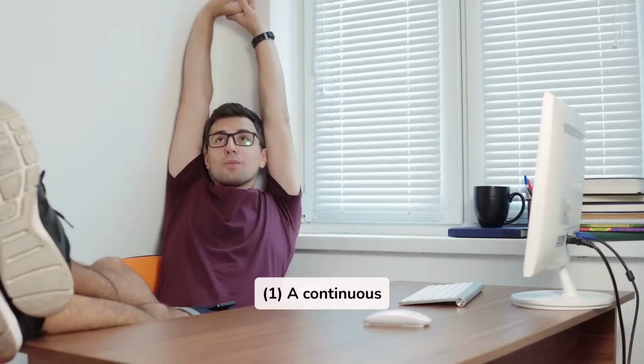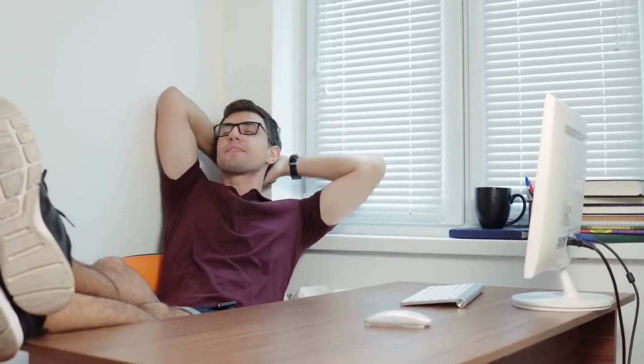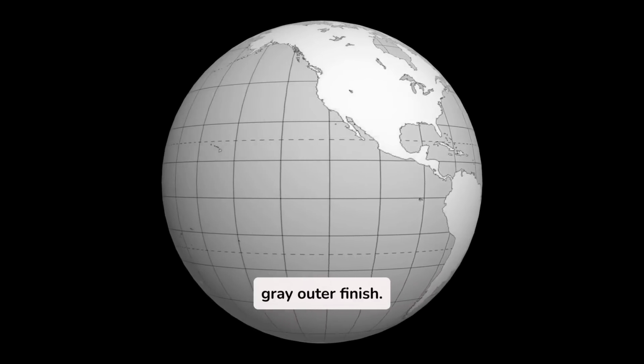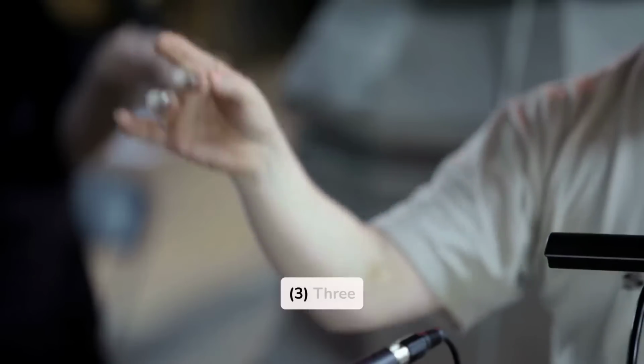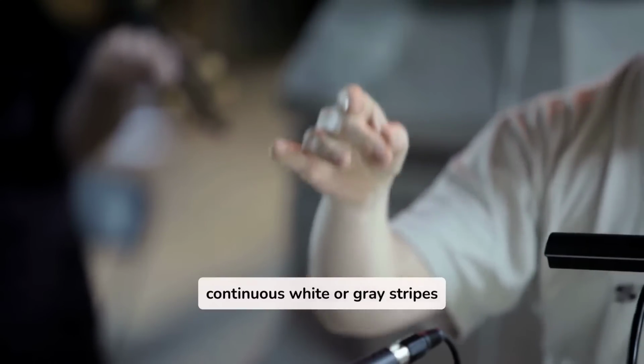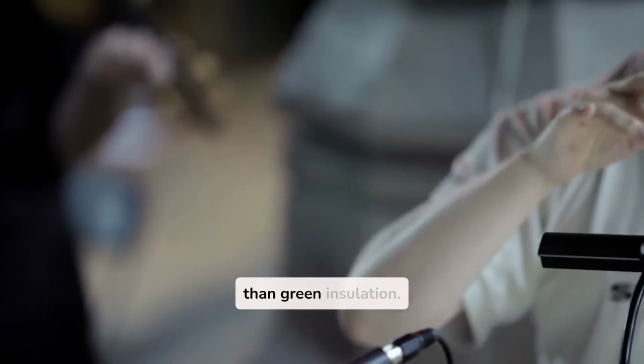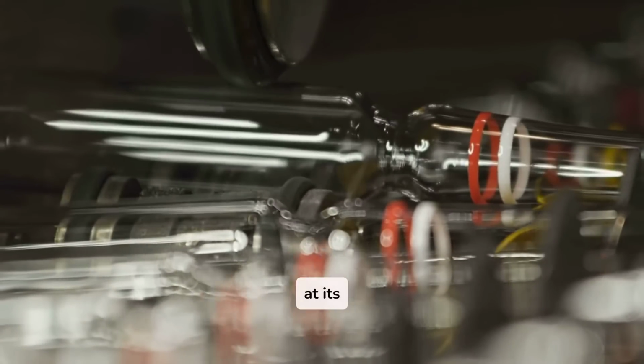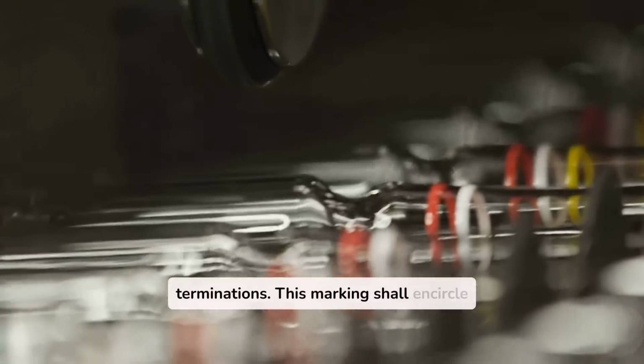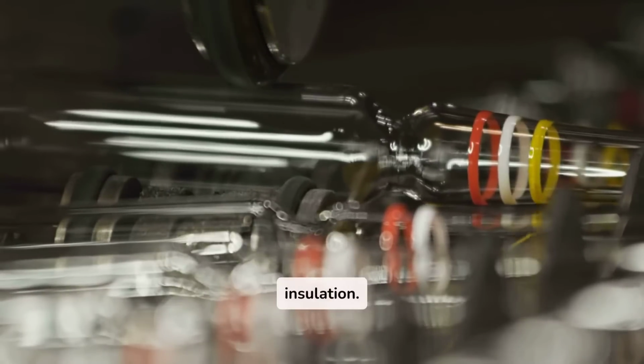1. A continuous white outer finish. 2. A continuous gray outer finish. 3. Three continuous white or gray stripes along the entire length on other than green insulation. 4. At the time of installation, be identified by a distinctive white or gray marking at its terminations. This marking shall encircle the conductor insulation.